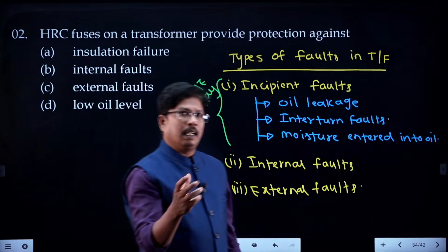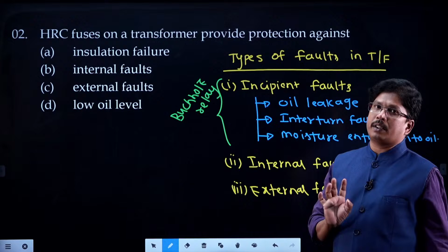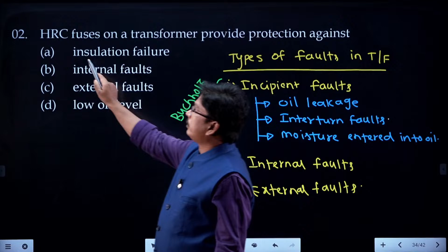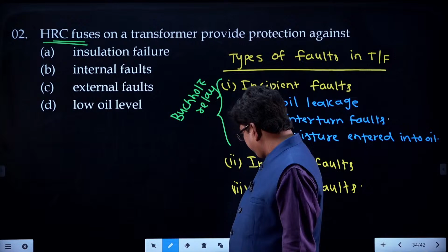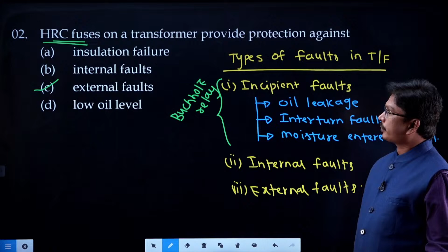For small internal faults, or for small rated transformers less than 1 MVA, we can use the Buchholz relay. For large rated, we can use the percentage differential relay. But whenever external faults occur, we can use overcurrent protection. The overcurrent protection is given by fuses. So the fuse is giving protection from external faults. It is not the low oil level. Low oil level is an incipient fault, and that is given by the Buchholz relay, right?